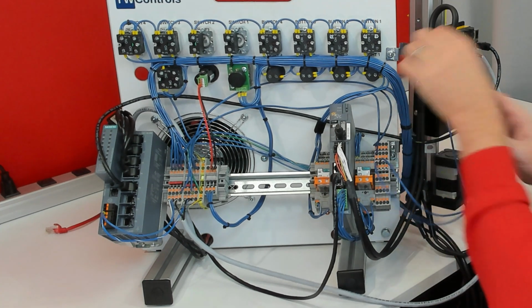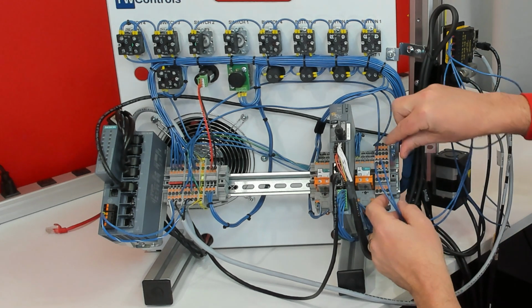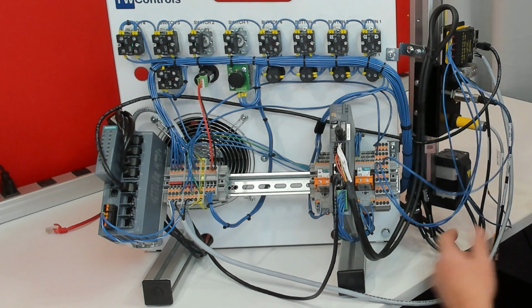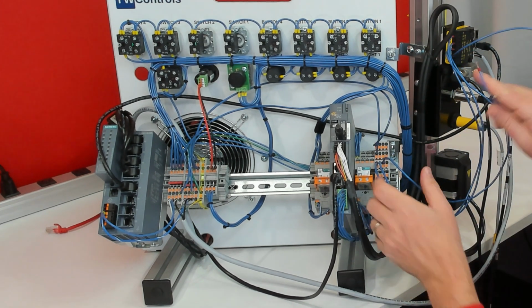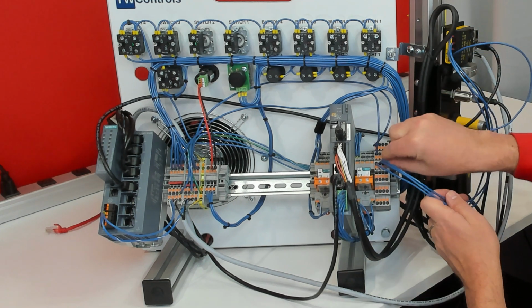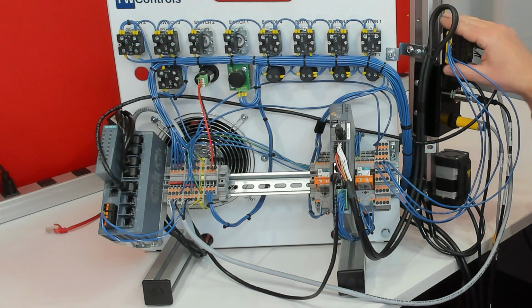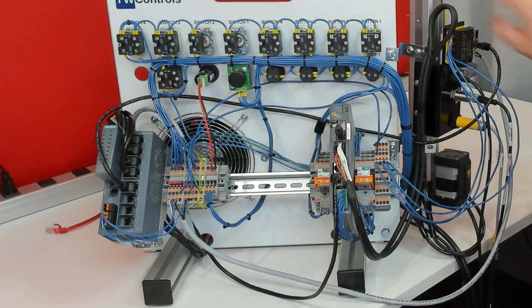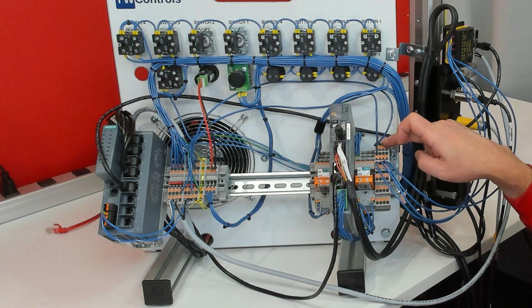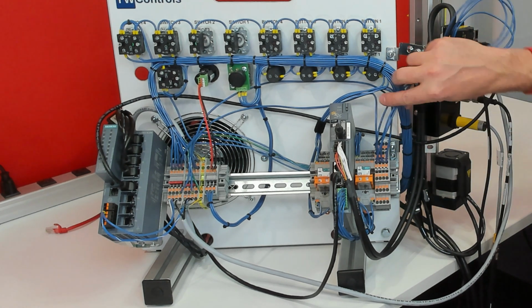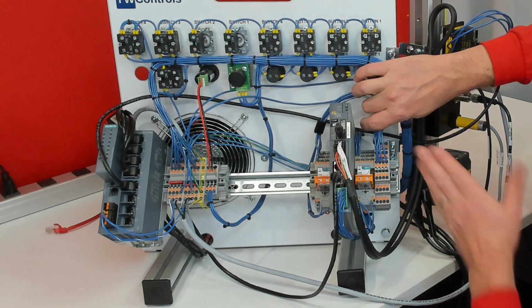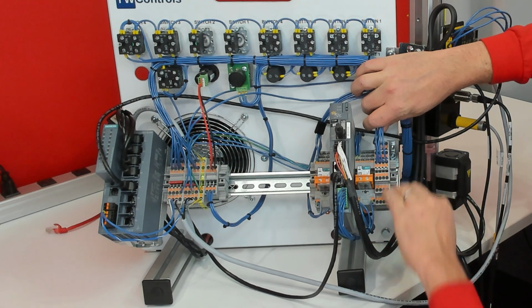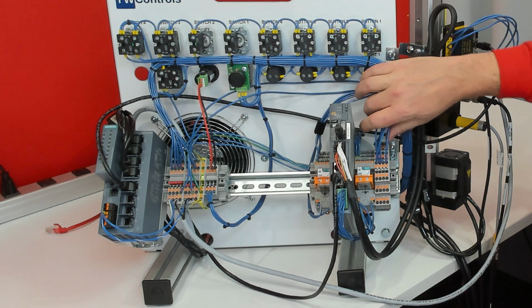We're going to take number three, and put it on the third one of the upper level. And we're going to take number four, and put it on the fourth one of the upper level. Now, we're not actually going to land any other wires on the IO link module because we're getting our plus 24 from right here. So this would simulate really your power wiring inside of the control panel, and the bottom part is where your field wiring would go.